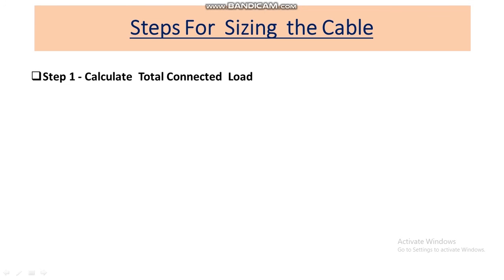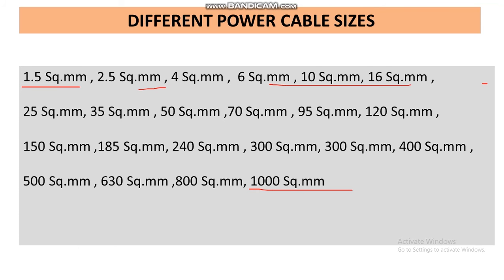Now let's move to the steps. There are four steps to follow for sizing the cable. First, calculate the total load of the feeder or circuit. Second, calculate the current. Third, calculate the cable size. Finally, select the cable size as per what is available in the market, because the exact calculated value may not be available. Cable sizes available in the market range from 1.5 square mm to 1000 square mm.